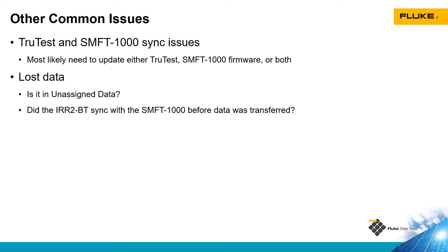An interesting thing about the SMFT-1000 with the IRR2: once you connect the two, the IRR2 will start data logging. When you connect the IRR2 to the SMFT-1000, it will ask you if you want to synchronize the clocks by hitting the up button — always do that. Synchronizing the clocks allows the SMFT-1000, if it loses connection to the IRR2, to synchronize that data once reconnected, importing the irradiance and temperature data from the IRR2 and correlating it with your test results.